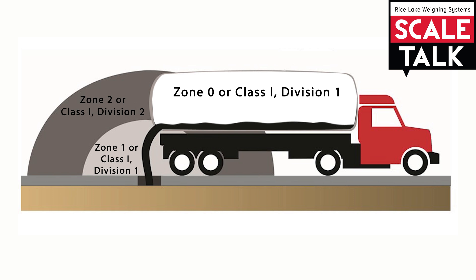In the darker gray area we have zone 2 division 2. This is an area defined farther away from the hazard. Under normal operating conditions the hazard is not there. As a comparison, think of your garage at home where you might store a gas tank. Under normal operating conditions the hazard is protected by the tank, but if you have a spill, now it's a potentially hazardous area because if you have a spark it could ignite. So the hazard is not normally there but it could potentially turn into a hazard.